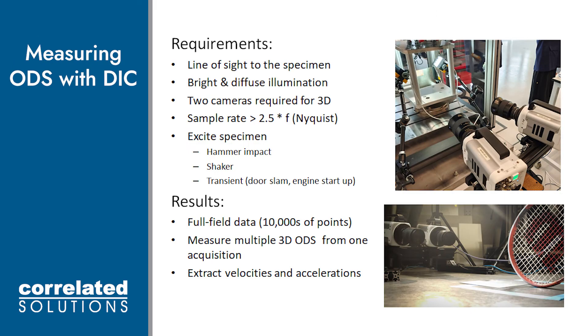There are some requirements needed for this measurement technique. The cameras need a clear line of sight to the speckle pattern. We need bright and even lighting across the speckle pattern. We want to capture images at about two and a half times the highest expected frequency. And the test should only last a few seconds at most. If we can get all of these things, the results will show full field color contour plots of 3D operational deflection shapes, which also allow us to extract local velocities and accelerations.